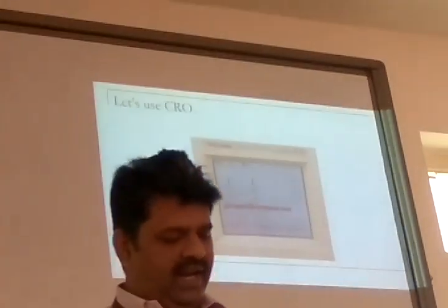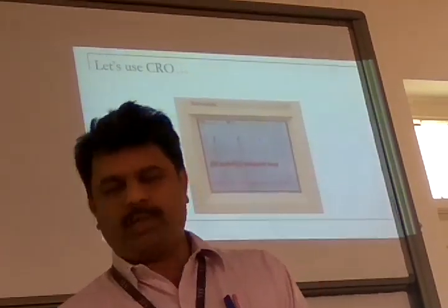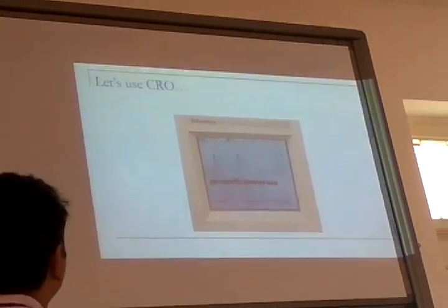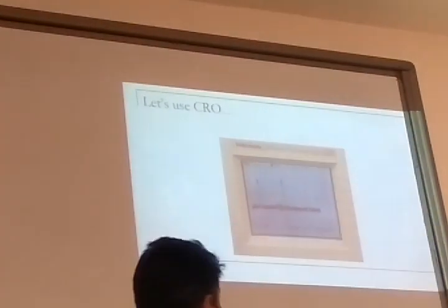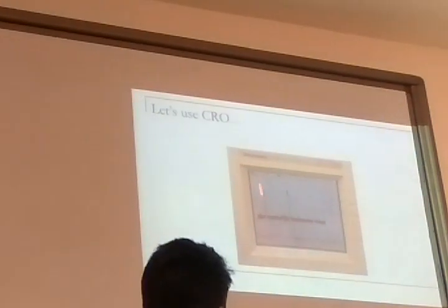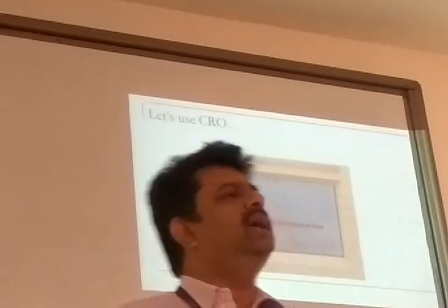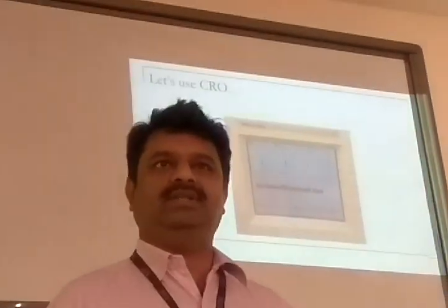So I am expecting either a perfect straight horizontal line or with a small slope of increasing or small slope of decreasing. But I am expecting a line. But what is it I am getting here? A lot of noise here. Lot of noise. And also in between there are bigger peaks. Even this I can eliminate, but there are some bigger spikes that's coming. Again, these are all noise that's picked up from the ambience.